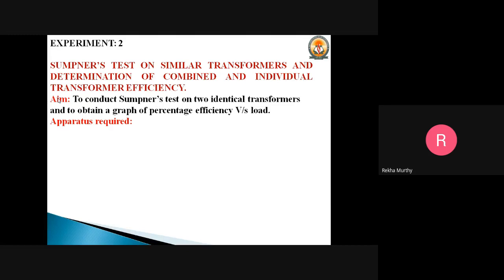So why do we call this the back-to-back test? That is because one transformer is loaded on the other, hence it is called the back-to-back test. SUMPNER'S test provides the data for determining the regulation, efficiency, and also the heating under load conditions. And here we are going to make use of two identical transformers.